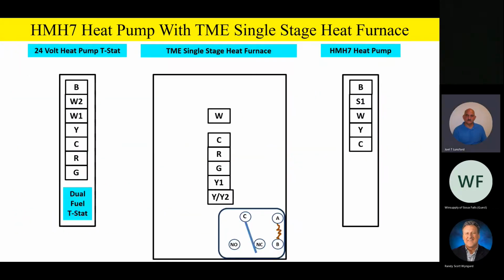Okay, so as we did before, we're going to go ahead and talk about this wire for wire. You're going to notice that on the furnace, it actually has hard screw terminals, and they're going to be labeled a little bit differently. For instance, on this TME furnace, we're going to have a Y1 and a Y/Y2 call for our cooling calls, but it is a single stage furnace, so you're only going to have one W terminal on the furnace. So let's go ahead and wire this thing up.